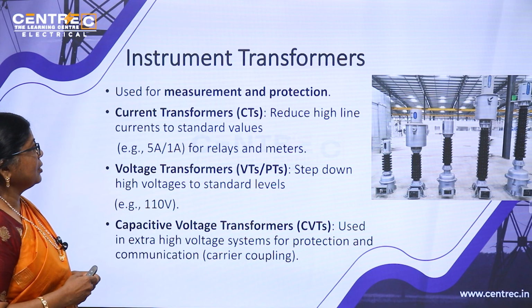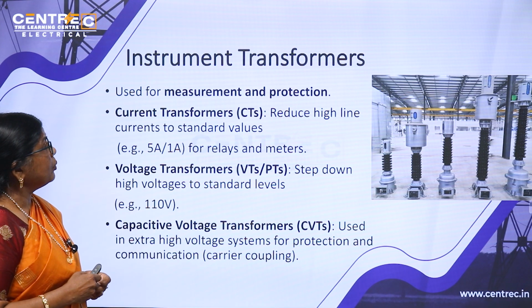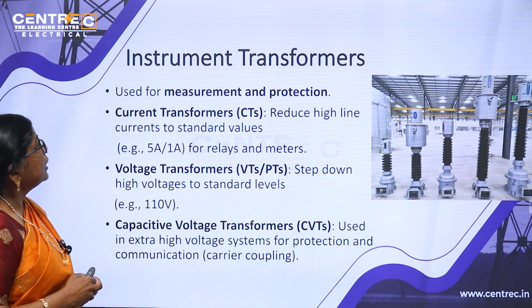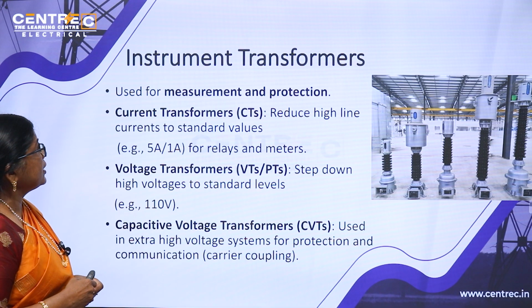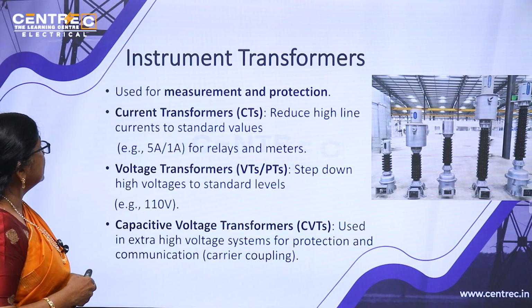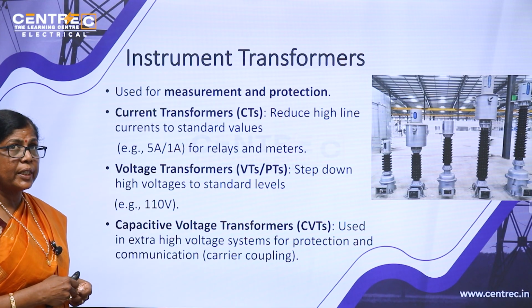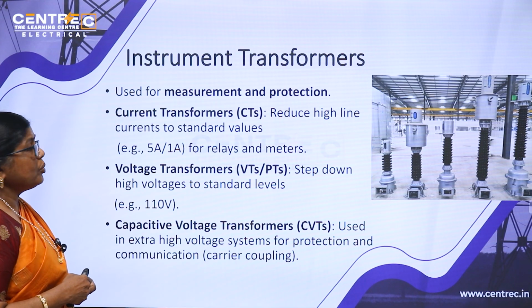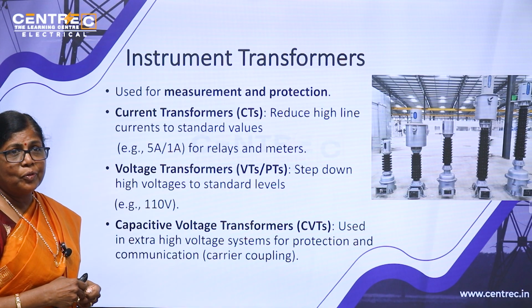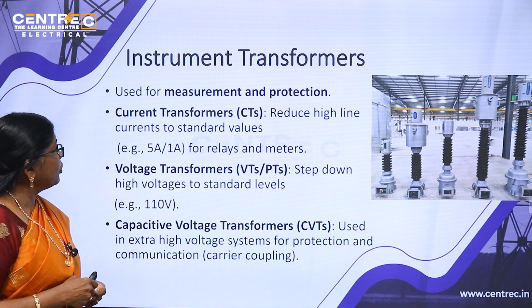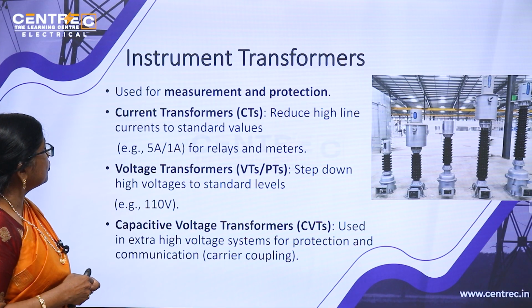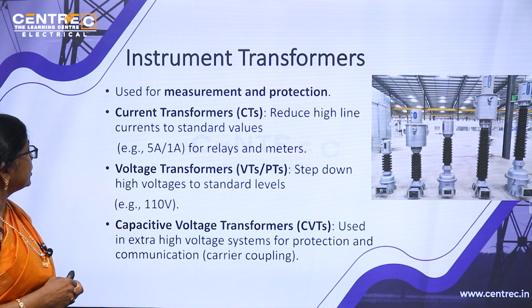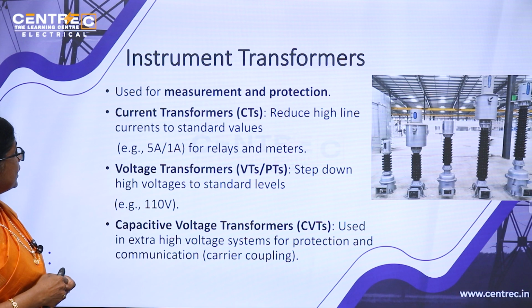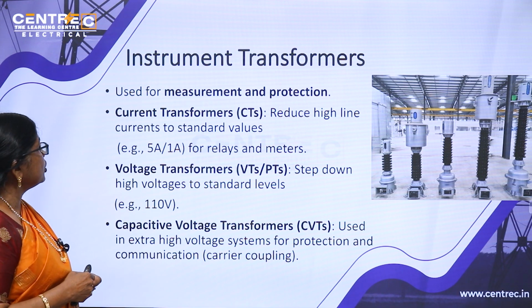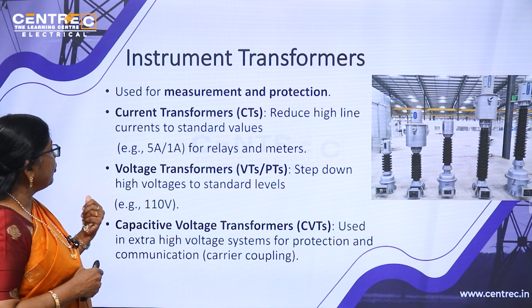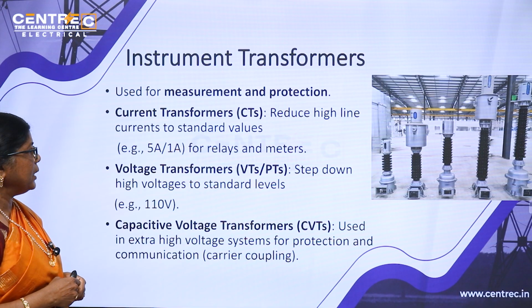Instrument transformers. We have different transformers. This is one of the important transformers used in substations and generating stations, for measurement and protection. Because we cannot use an ammeter directly for measuring this high current, we use instrument transformers for measuring high current and high voltage. Current transformers reduce high line current to standard values, for example 5 ampere or 1 ampere for relays and meters.